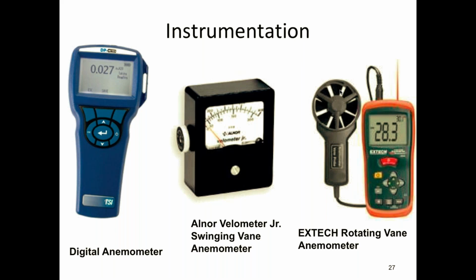That's the velocity of air that's moving through that point. Move out and double that distance. Stop there. Hold on a second. It's not even going fast enough to spin the blade. Okay. One of the interesting things you're going to find about exhaust ventilation is that if you get only about a foot away from this duct, you almost can't feel any suction at all, right?